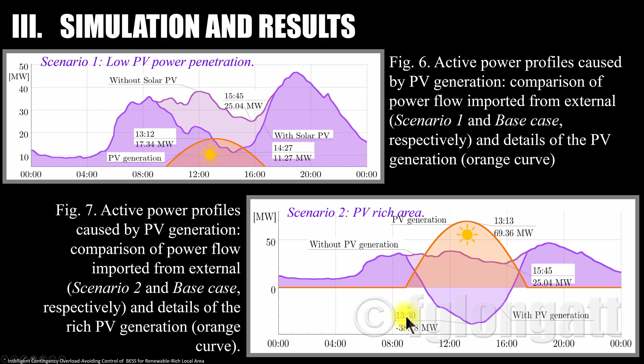But now let's examine what is the situation when we start to look into the loading of the transmission line. Well, scenario 1, if we have some PV generation that is a low penetration, well, you can see here how the small power plant is allowing to reduce the loading of the transmission line. You can see here how the loading is below 20% around 2 p.m. when you compare with the base case that was around 50%.